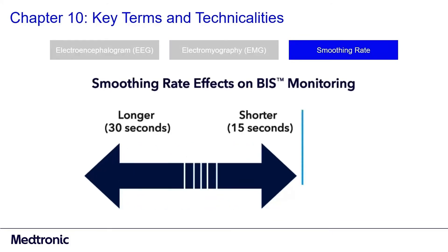Smoothing rate. The smoothing rate is the averaging of time over a set period in order to prevent excessive fluctuations. The BIS monitoring system gives users an adjustable period of time over which artifact-free data is analyzed and used to calculate the BIS value. Typically, the time period is set between 15 and 30 seconds, but to understand what is ideal for your clinical setting, please refer to the BIS operating manual.